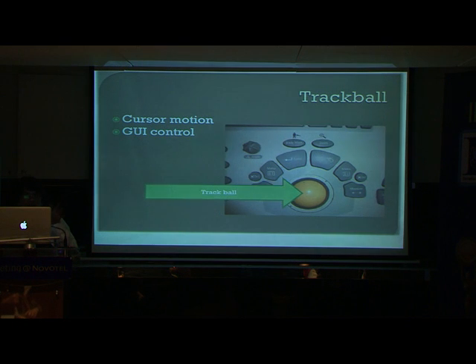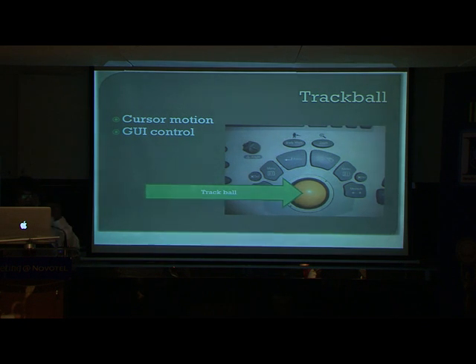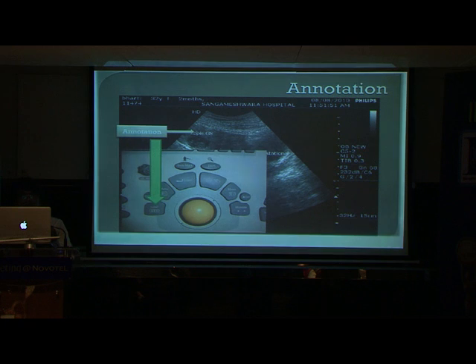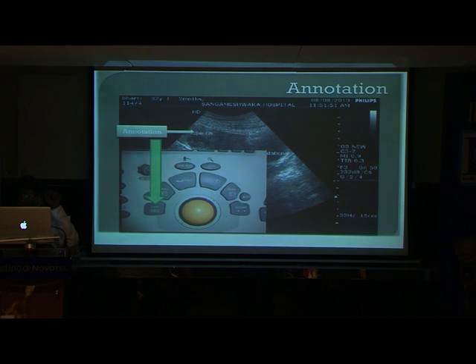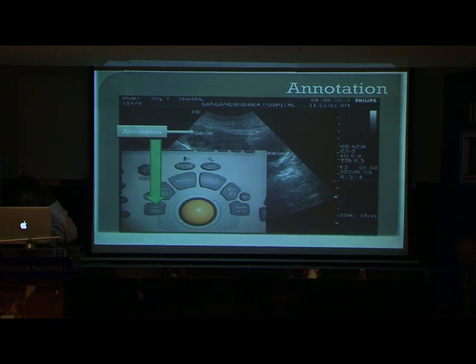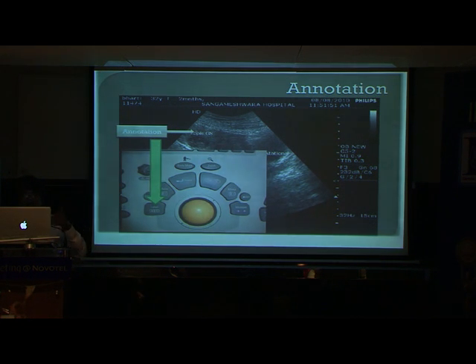The trackball on the machine can be used for the cursor when labeling something during an intervention for documentation purposes, or to apply software on-screen. Annotation is very important — it is the documentary evidence that proves your procedure. For example, when performing a femoral nerve block, you annotate: this is the artery, this is the vein, this is the nerve, and your needle is going inside the sheath. Annotating creates documentary evidence of your procedures.